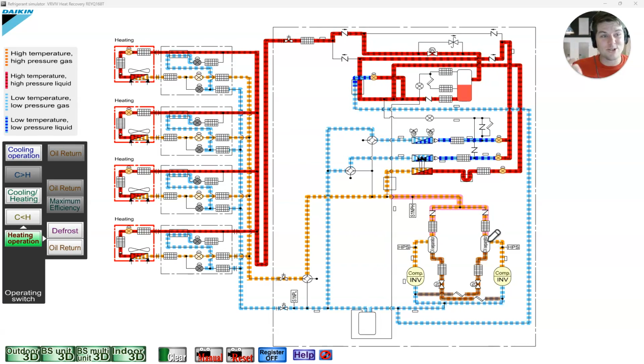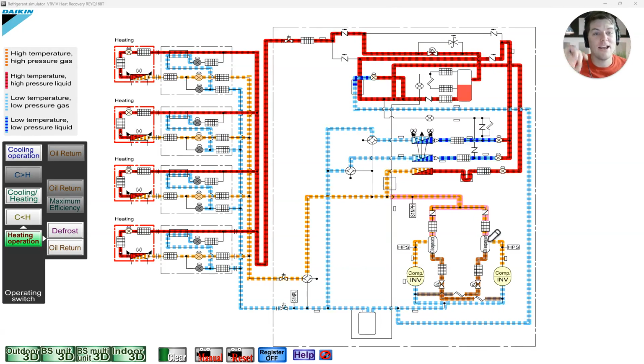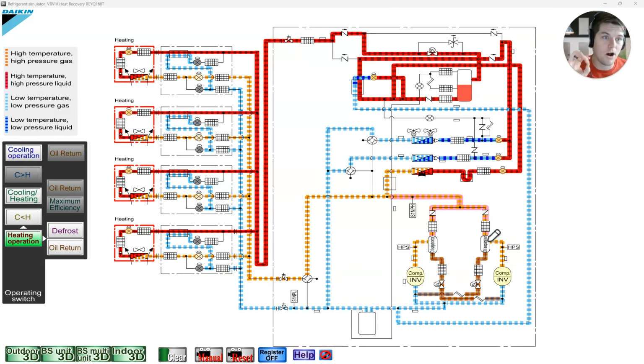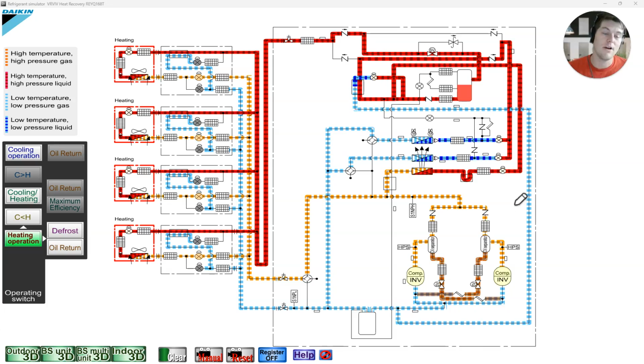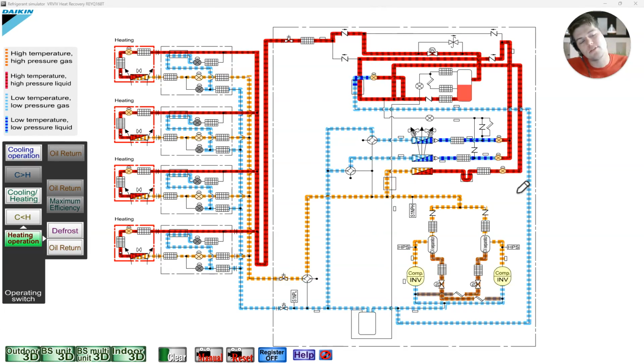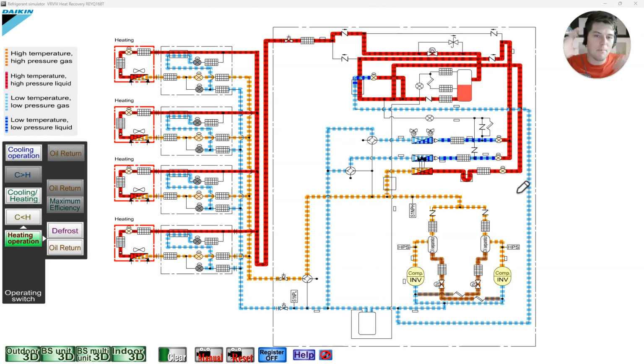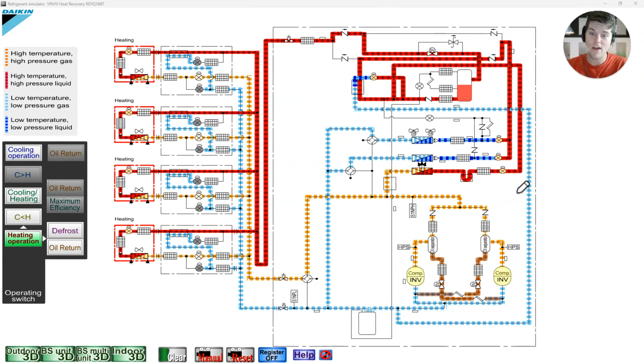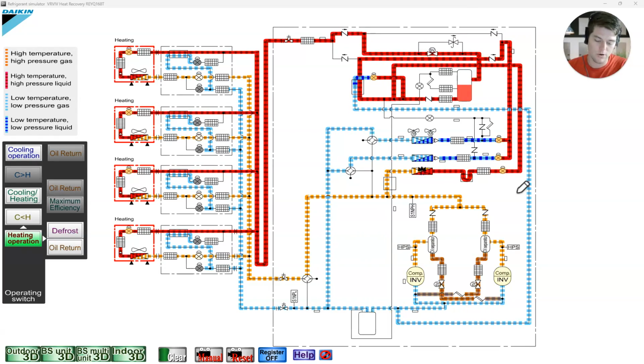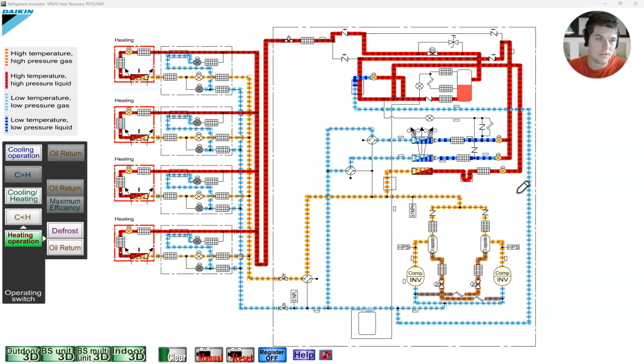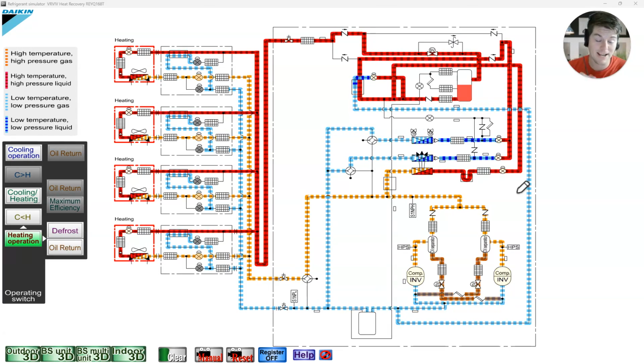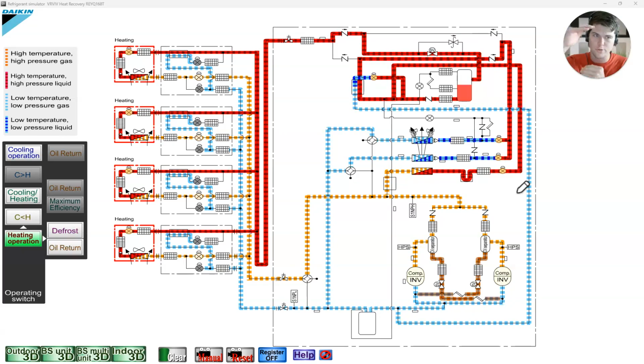They don't teach you this in school. They don't teach you this at the factory. This is extreme undercharged on the system, right? And you'd say, well, Roman, what about valve pulses and all this stuff? I don't need it because I see this, right? If I'm this far gone, there's no point in going any further to conclude or diagnose or peel this onion back anymore. This system is severely undercharged to the point where we're probably not getting any oil back, which is why our discharge superheat is through the roof, but also the quality of vapor sucks.